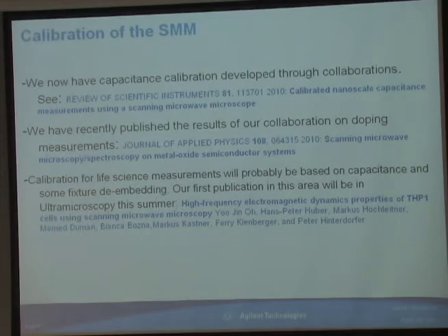What they built was a highly doped silicon substrate, put different heights of SiO2 on it, and then different pad sizes on each staircase. They built 3 or 4 orders of magnitude of capacitance centered in the femtofarad region, which allows us to touch the AFM down to each of those and draw a calibration curve, because those capacitances are defined geometrically - so you know exactly what they are, assuming you can measure the geometry - and then you have something you can convert to a calibration curve for the instrument. So now we can do absolute capacitance calibration.